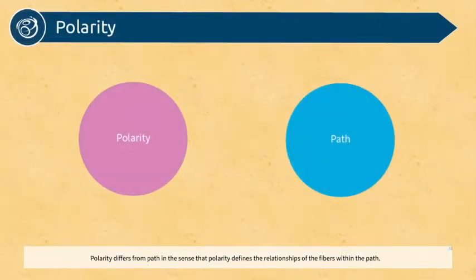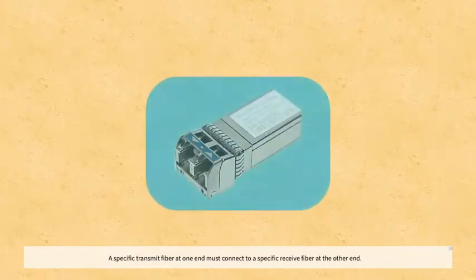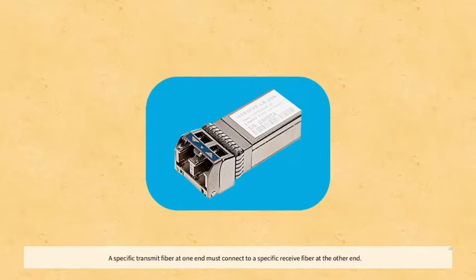Polarity differs from path in the sense that polarity defines the relationship of the fibers within the path. A specific transmit fiber at one end must connect to a specific receive fiber at the other end.